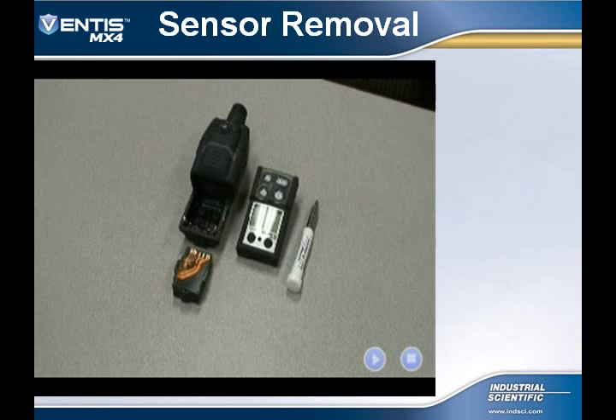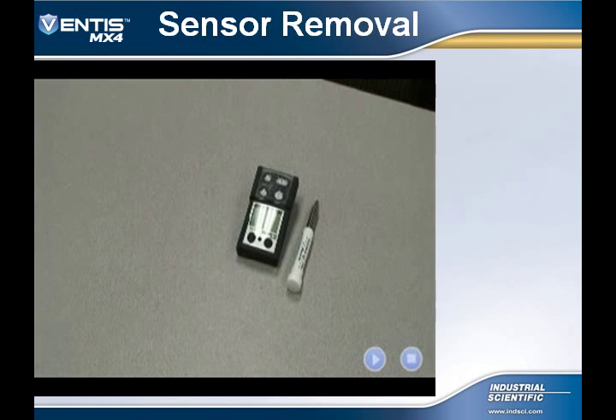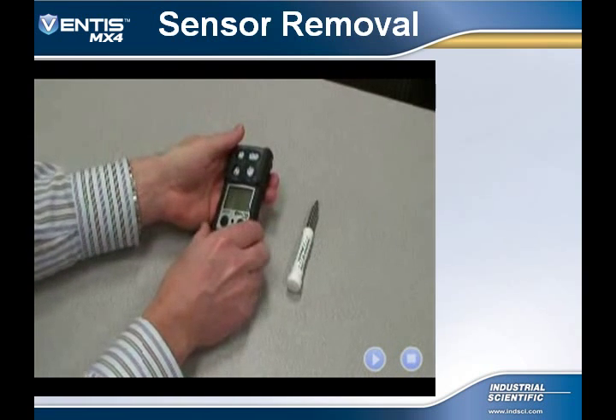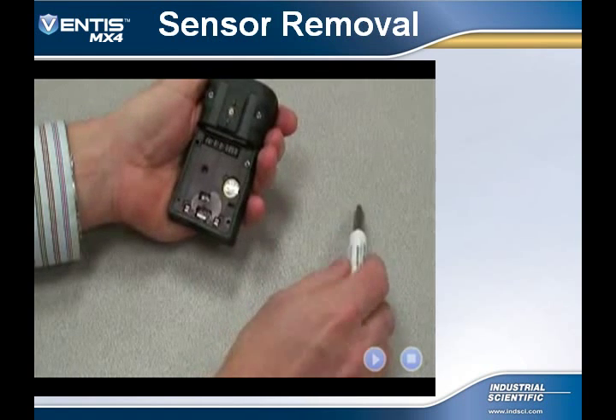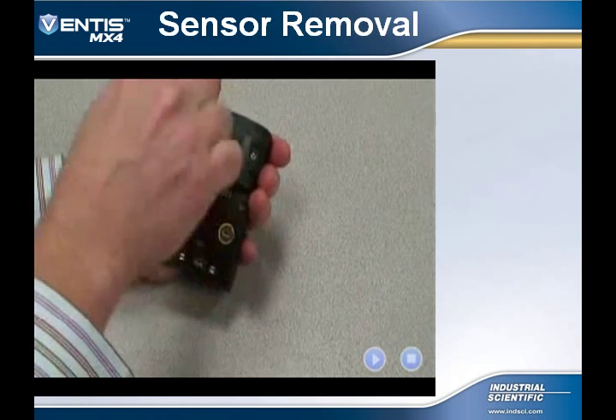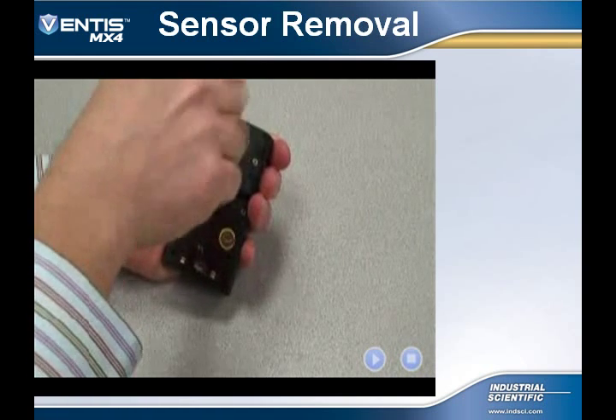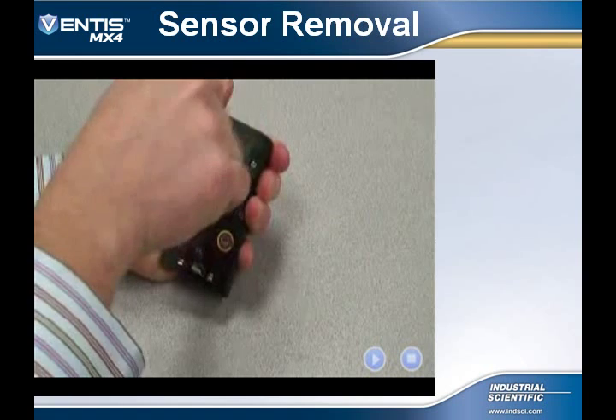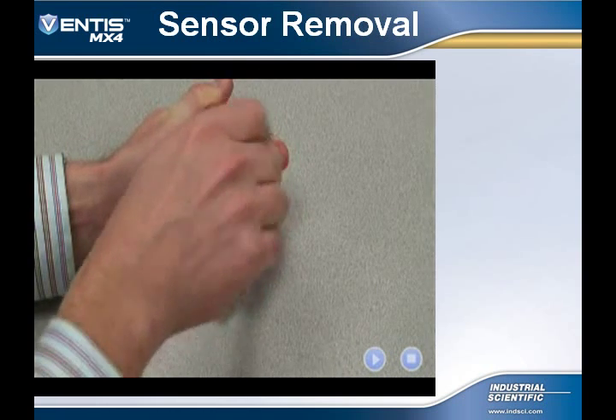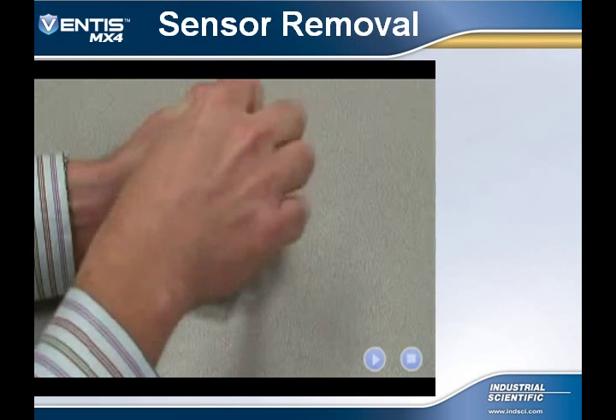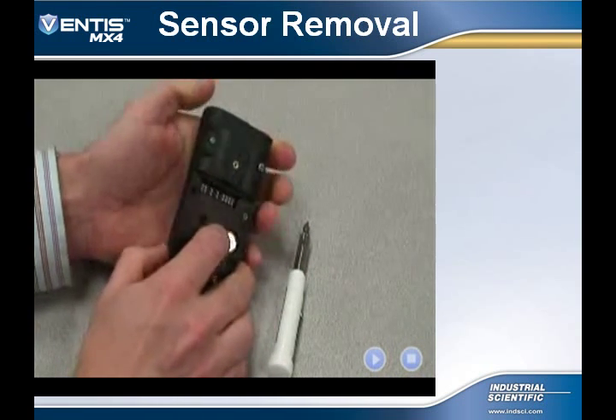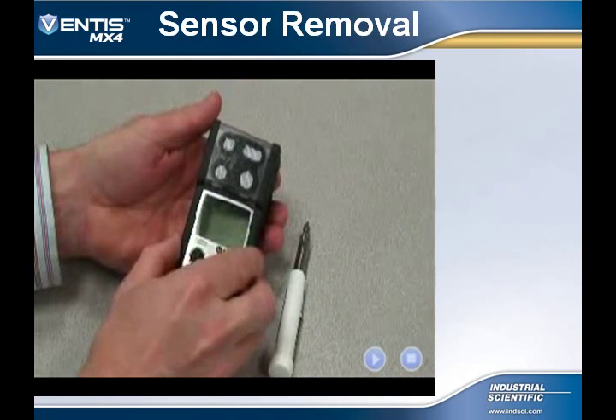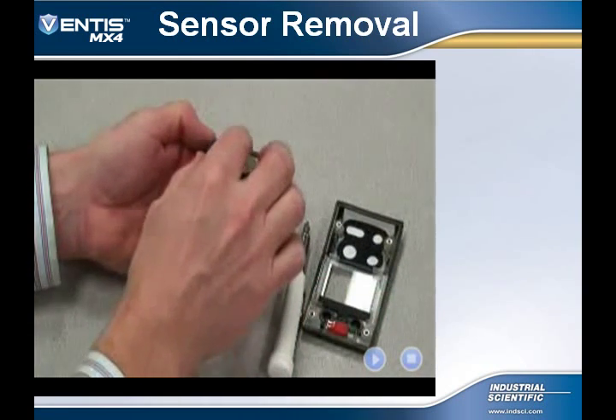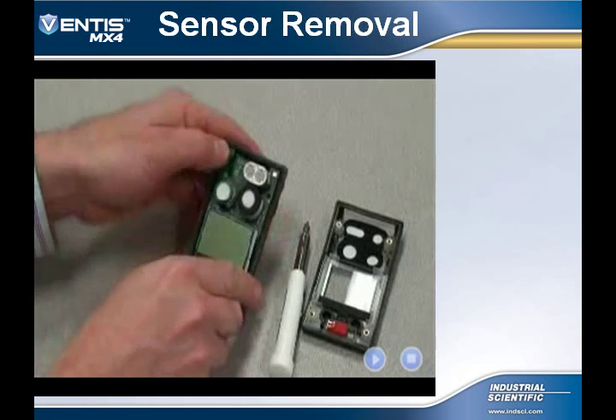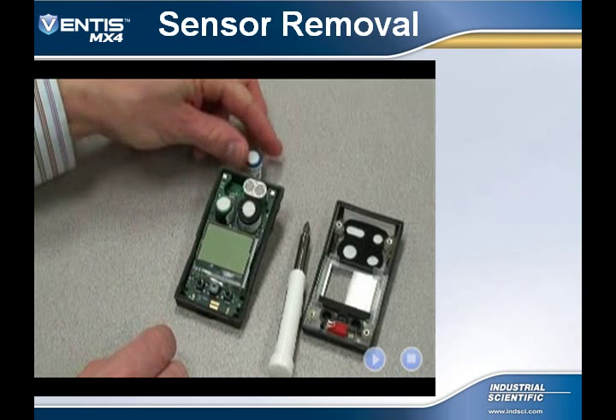This video demonstrates how to remove a sensor from the Ventis MX4. To remove a sensor from the MX4, follow the previously mentioned steps, and once the 4 captive screws are loosened, remove the instrument from the pump housing. Rotate the instrument on its back and remove the 2 remaining captive screws. Flip the instrument to its front and separate the 2 case halves to gain access to the sensors. Simply pull the sensor from its connection.